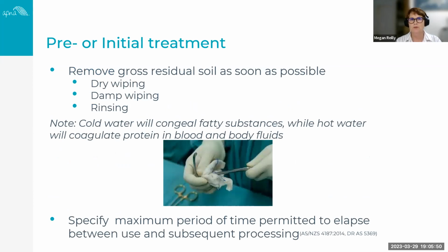We're aiming to remove any gross residual soil as soon as possible at the point of use. So that can be done through dry wiping, damp wiping, or if you are able to move those used RMDs straight through into your reprocessing area, you can rinse them in the dirty sink. Remembering that cold water will congeal fatty substances, while hot water will actually coagulate protein in blood and body fluids and make it much harder to clean the item. Now, interestingly, in 4815, it doesn't state it at the moment, but in the current 4187, but also in the new draft standard, it refers to having policies where you actually specify the maximum period of time permitted to elapse between the use of the RMD and subsequent processing.